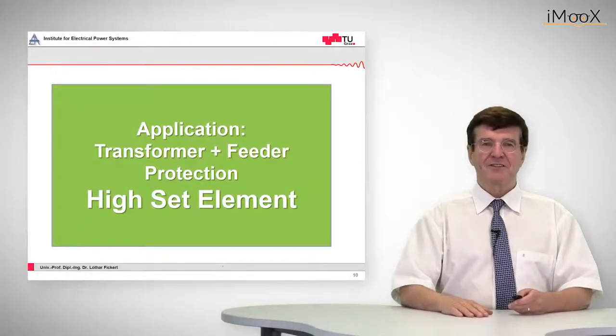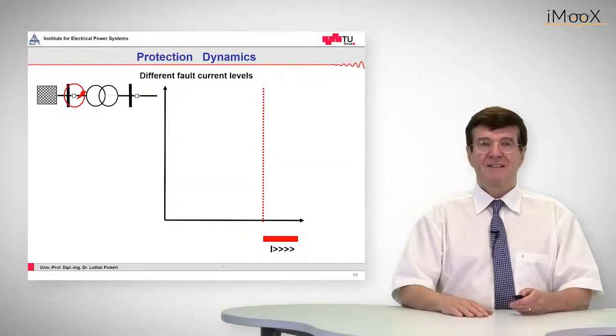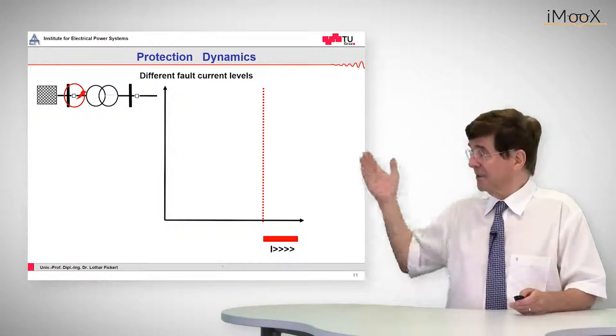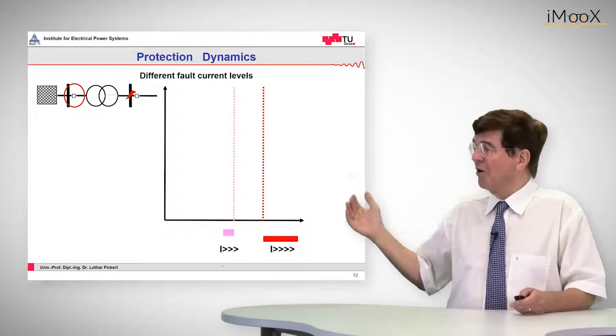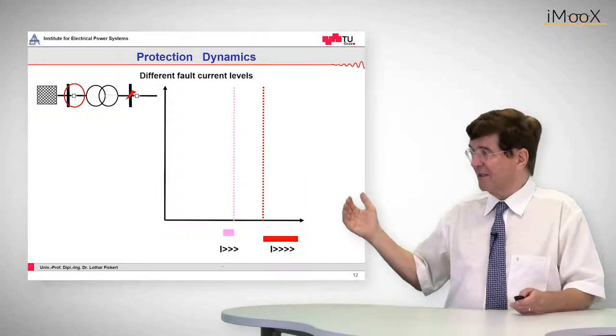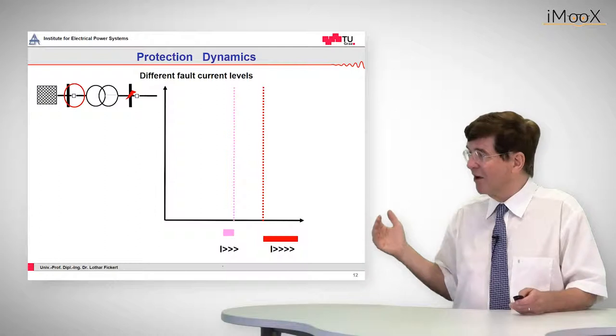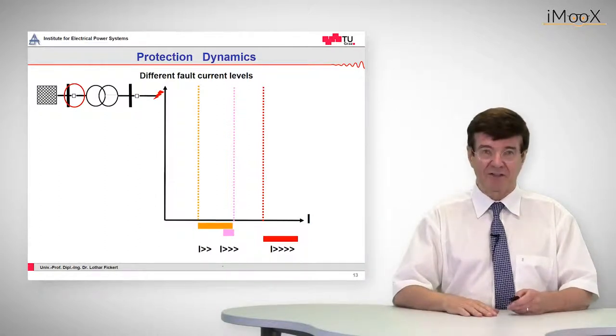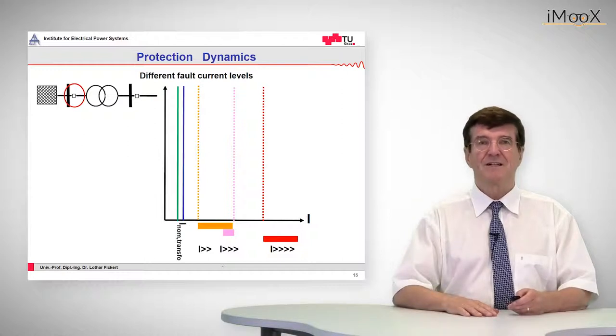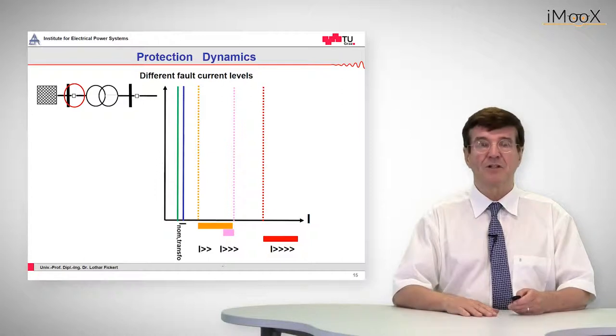Let's look into the high set element of the transformer protection. We have different fault current levels. The highest one is the fault current level upstream of the transformer. The lower one is downstream at the bus bar, for example, and the lowest one is the fault current level at the end of the longest feeder. For completeness, we should also include the nominal currents of the transformer and that of the feeder.